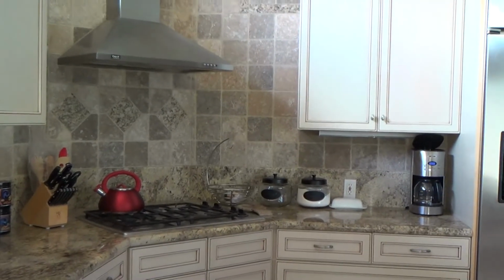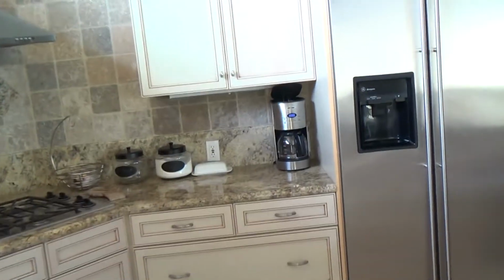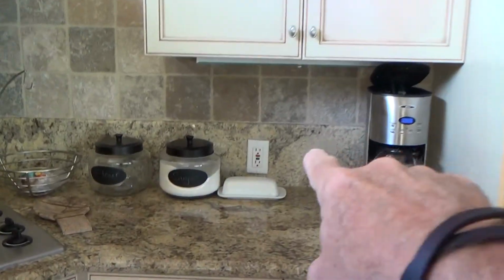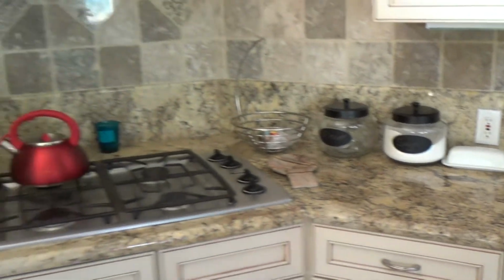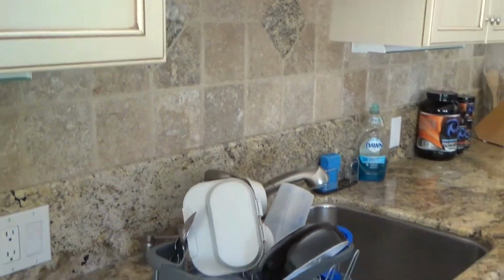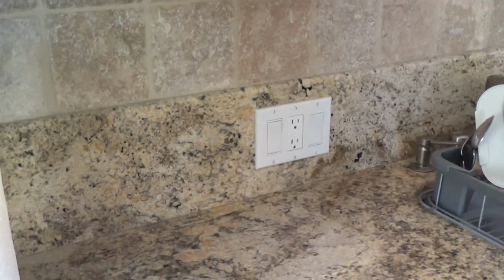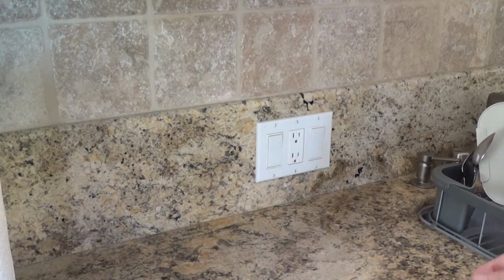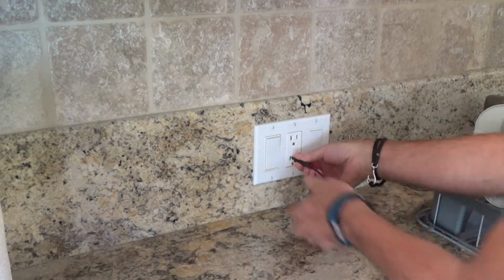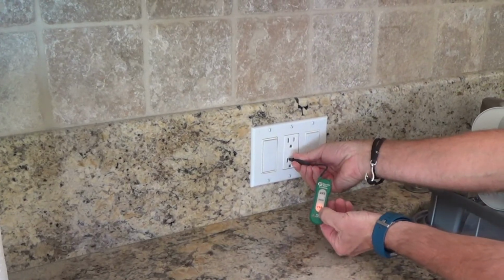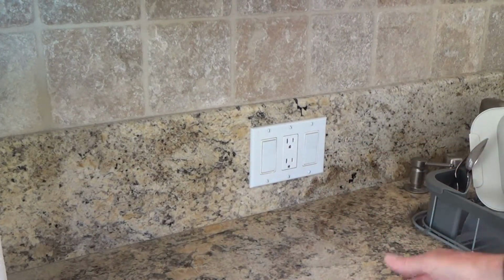So right now I've got the power, the breaker, on, because here's the other thing: if the breaker was off outside, that button probably would not reset. It might trip it, but it probably would not reset it, because you gotta have power. As far as I know, you gotta have power on there. See, we do have power here, okay?